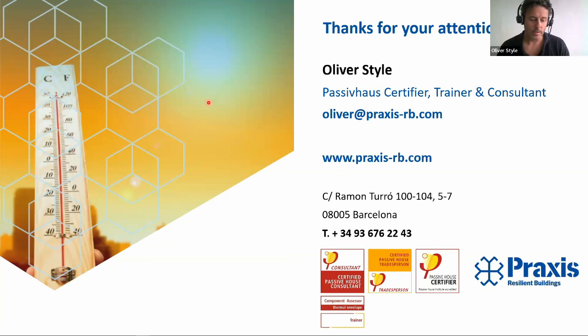The issue was simply that what I was presenting on the graph was measured air temperature, not operative temperature. Measuring operative temperature is complicated because you have to measure the mean radiant temperature, which requires a spherical radiant temperature sensor plus an air temperature sensor, and you'd need to do that in every room. The point was just to avoid confusion, because the PHPP uses operative temperature, but what I presented on the graph was air temperature, which is generally the cheapest and simplest thing to measure. So it was just that difference.